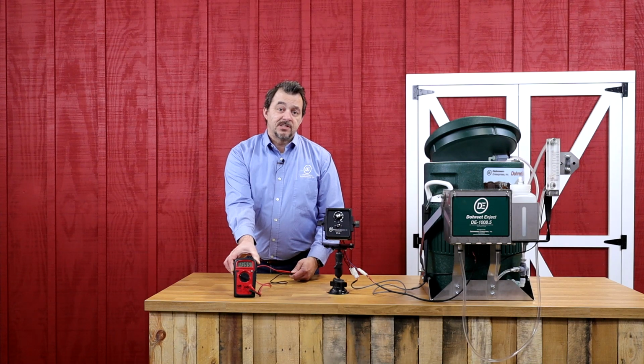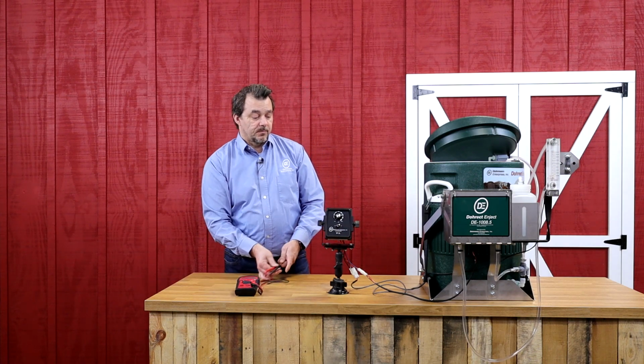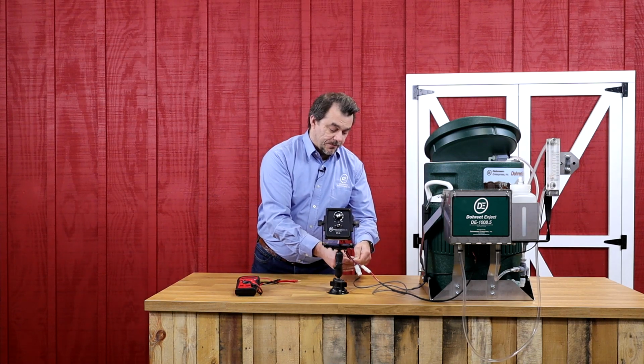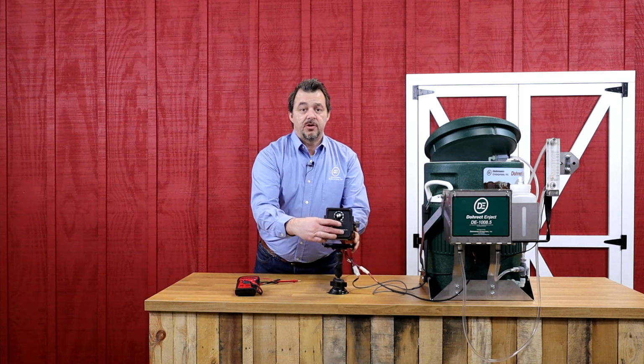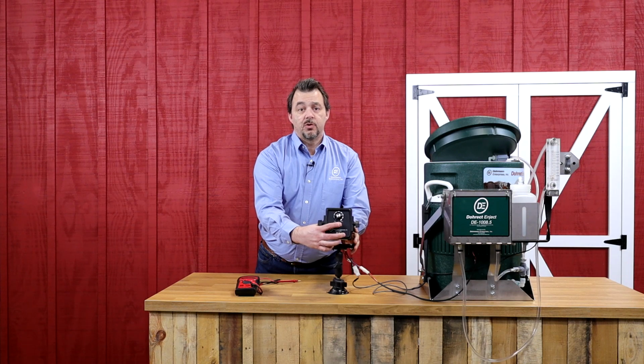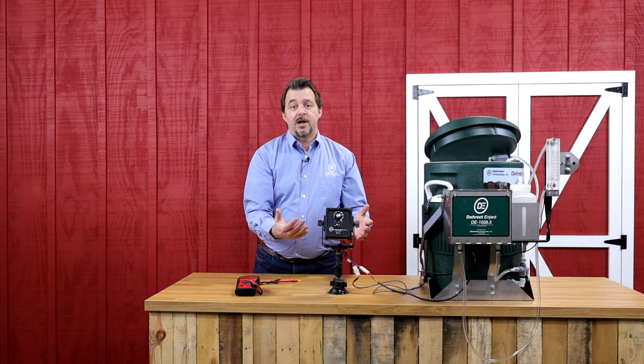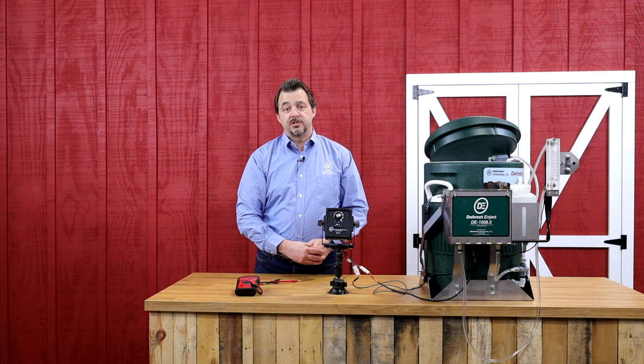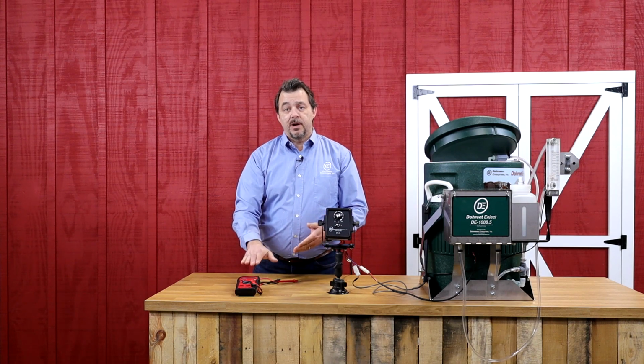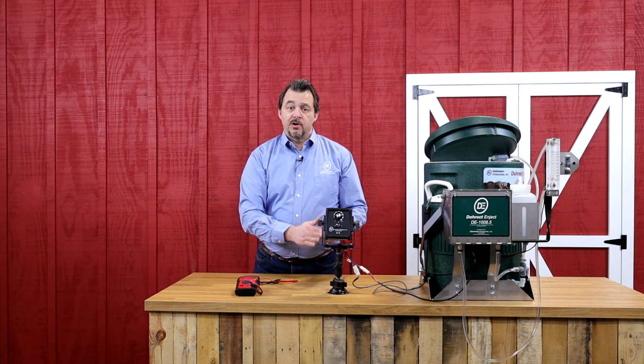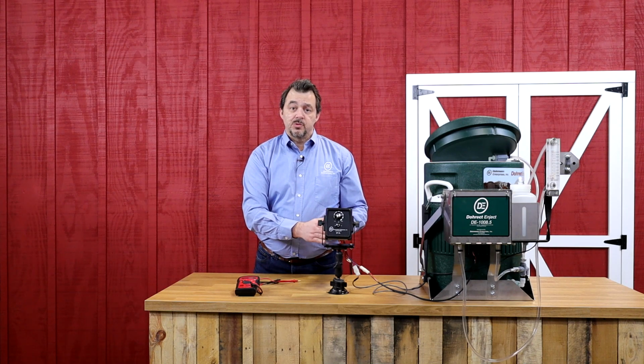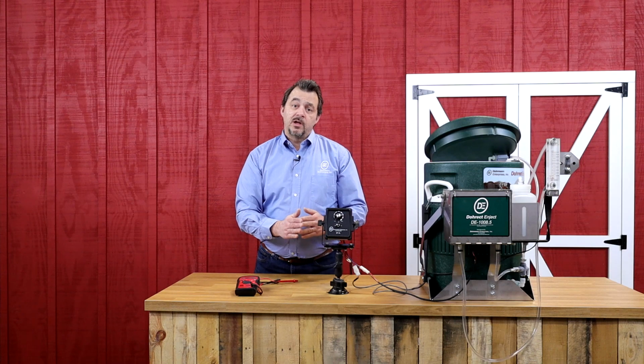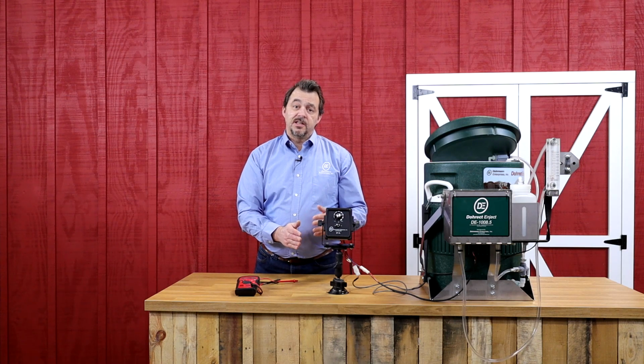So again, if it was wired this way and the pump was running backwards, that gives us an indicator of that. But because this is wired backwards, if we hook up the controller, which I will do right now, you'll see that we still don't have a functioning controller. The LED light doesn't come on because it's under reverse polarity protection. So we need to make sure that we're getting a positive reading on our multimeter using both our positive and ground leads or the pins within the wire harness. And then we also want to make sure that that voltage is ideally somewhere between 10 to 15 volts.